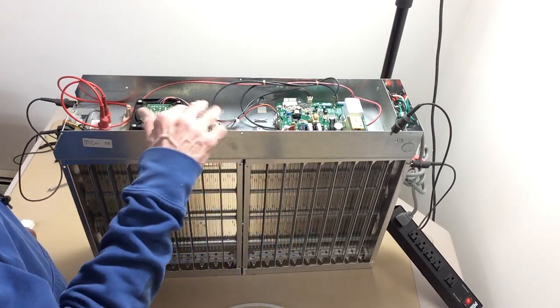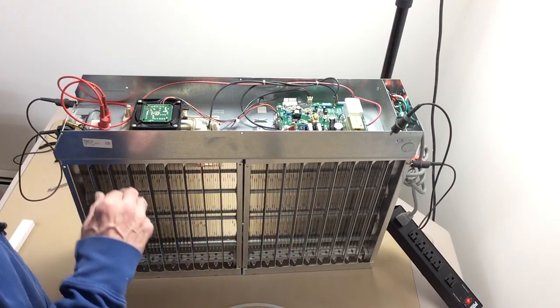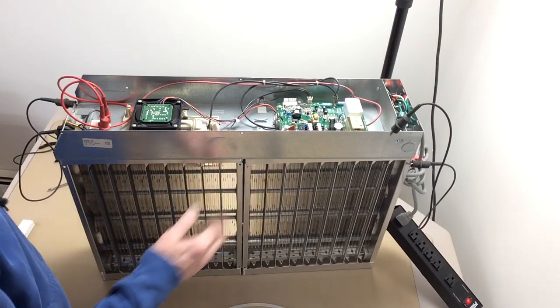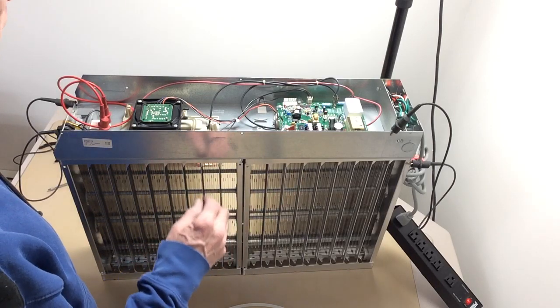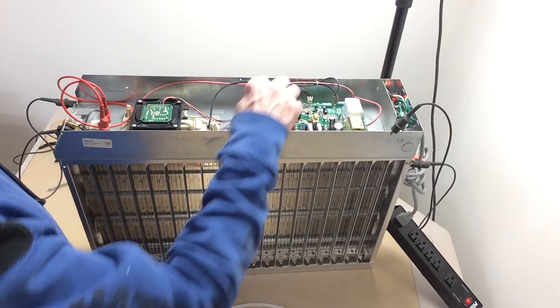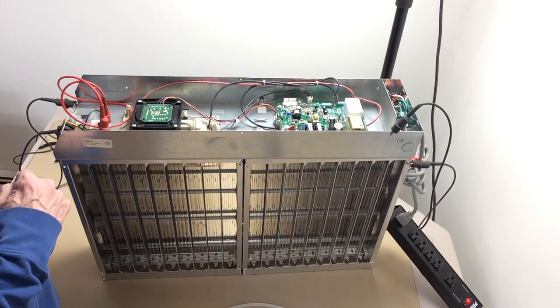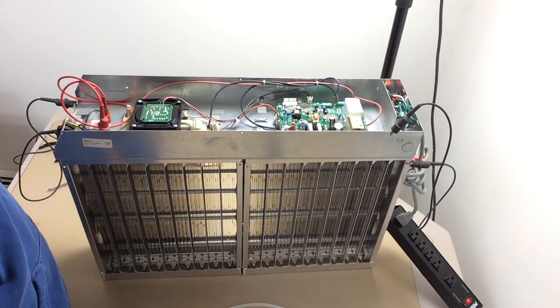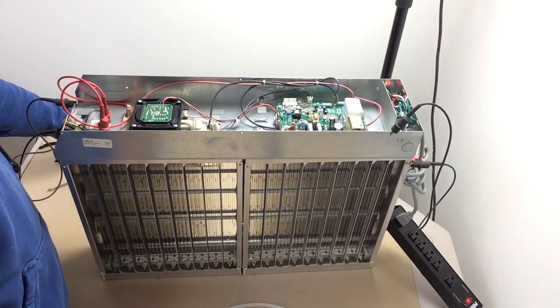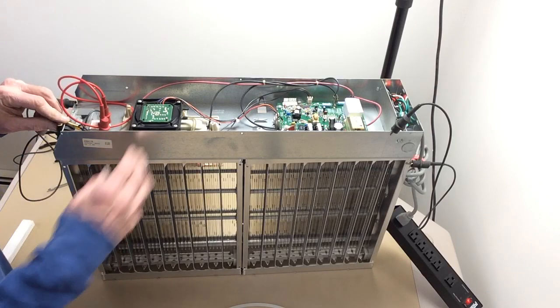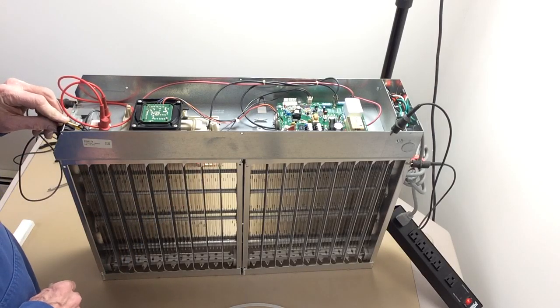If you just didn't need your airflow sensor anymore because you ran your blower all the time and the air cleaner was on all the time, something like that, you could just put that shunt there. Or you might have your blower connected to your air cleaner connected to the circuit board in the furnace that turns it on whenever there's airflow.